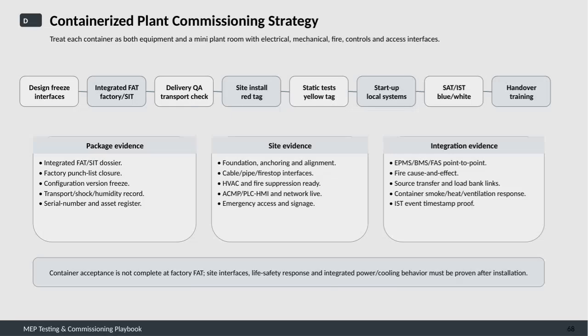process. This slide outlines a commissioning strategy for containerized plants, treating each container as both individual equipment and a mini plant room with multiple interfaces: electrical, mechanical, fire, controls, and access. The process begins with design freeze to lock-in interfaces, followed by integrated factory acceptance testing and site integration testing to validate performance in controlled environments.